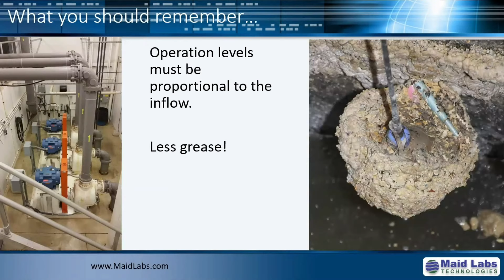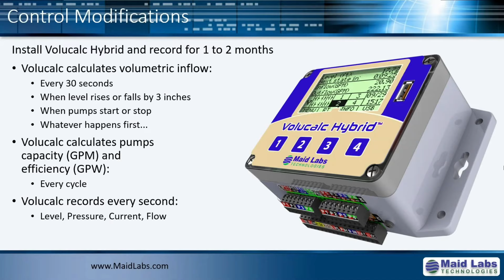This is the instrument that can be used to do everything I explained so far. Since we have an analog output proportional to flow rate in real time, you can feed that to your PLC and adjust it so that when the flow rate is higher or lower than a certain value, you adjust your levels based on that. But you need real-time flow for that, and this system does all the diagnostics I was explaining at the beginning, with all these algorithms built in. And we're talking about an instrument that is only 6 inches wide, 4 inches high, and 2 inches thick.